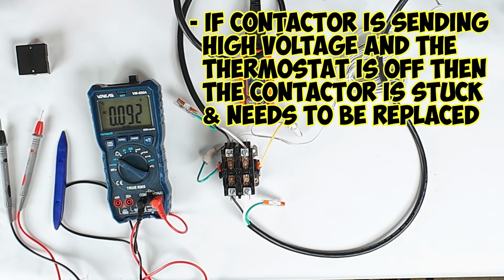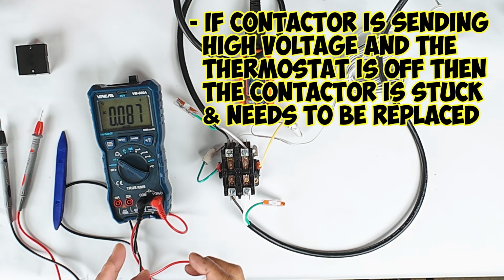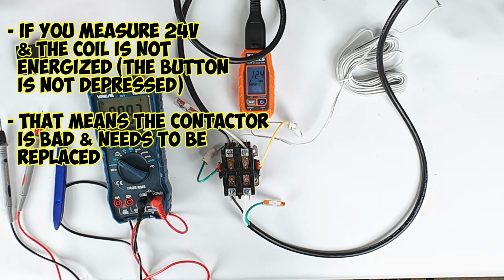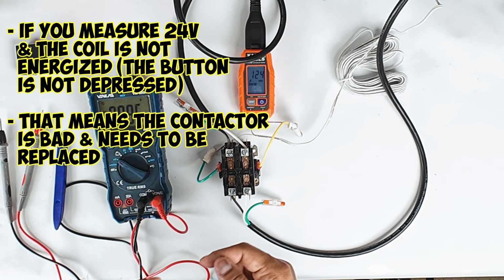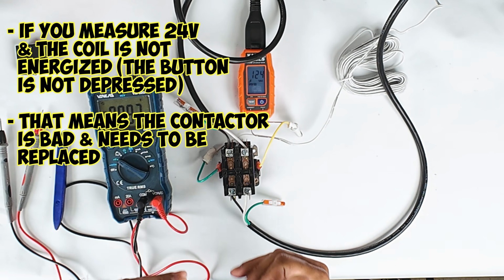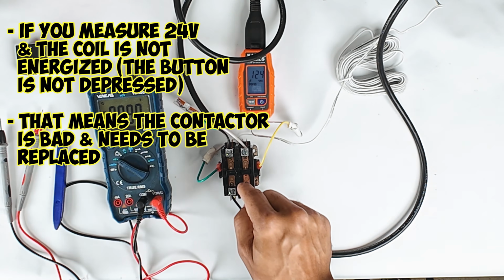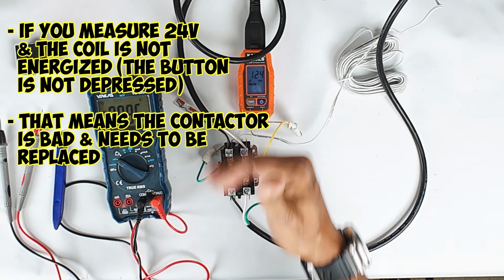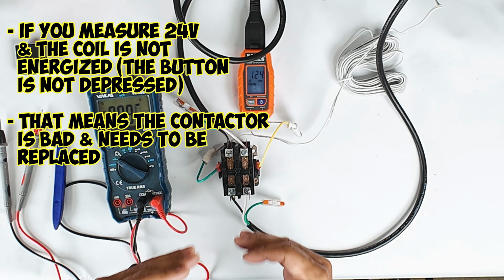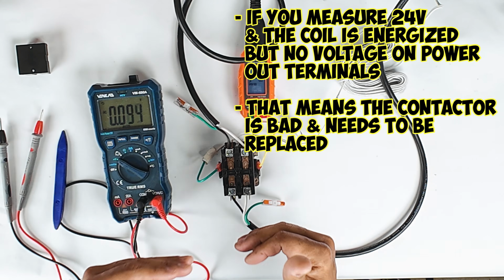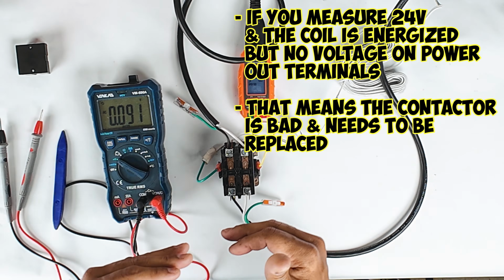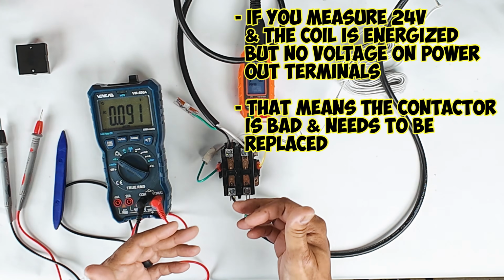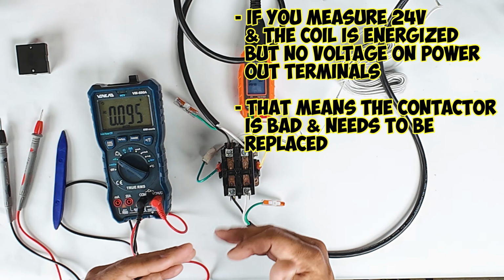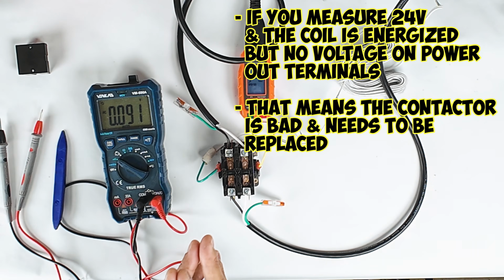If your contactor is energized without the thermostat being on, that means your contactor is stuck or it's bad. If you measure 24 volts and the contactor is not energized, meaning the button isn't depressed and you're not getting voltage through, it means that the contactor is bad. And the last step you want to check is if the contactor is energized and you measure the outgoing voltage, if there is no voltage, then the contactor is bad.